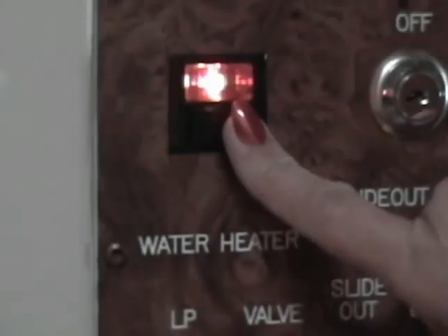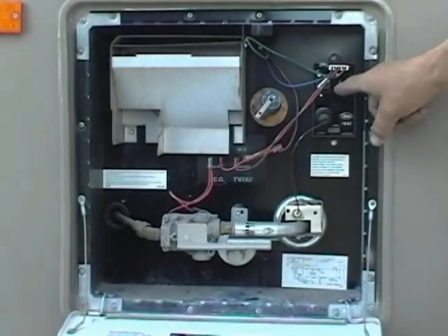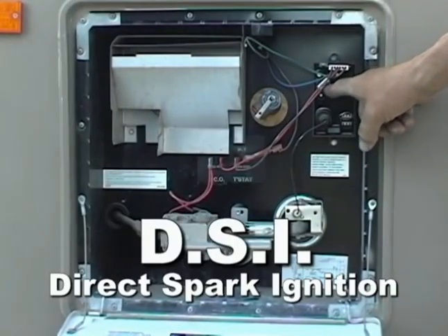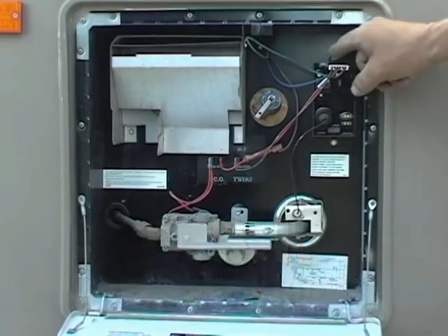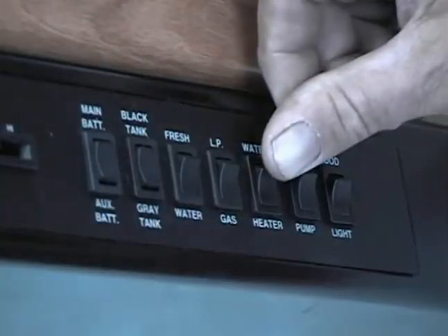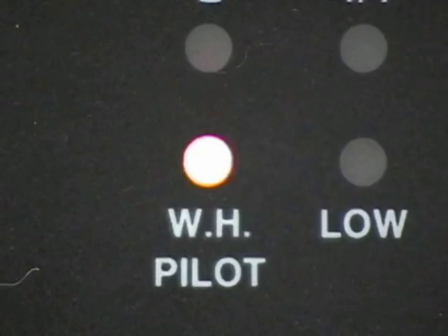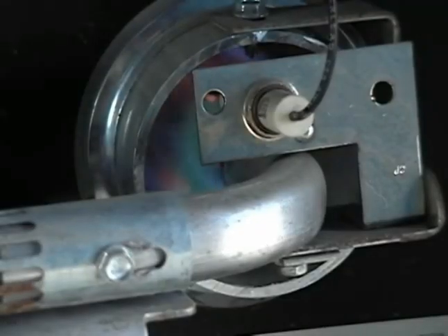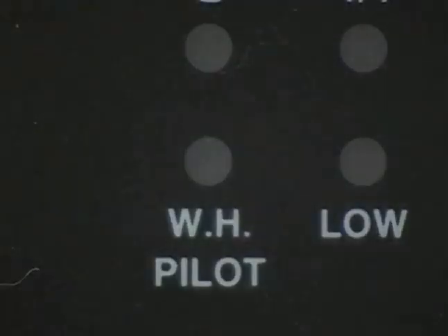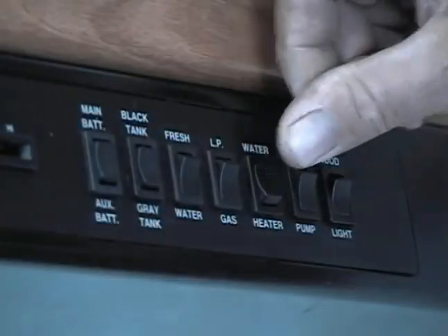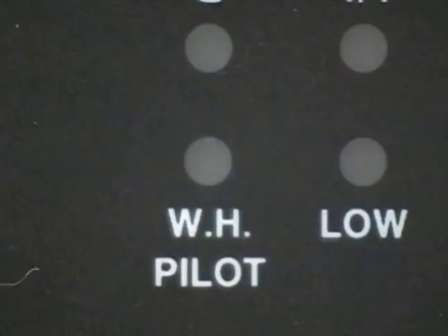Now let's move on to automatics, the DSI models, or direct spark ignition. These are very simple to operate. Make sure the propane is on and flip the switch. When you do, the light should come on. That's telling you that the process has begun. After a few seconds, the light will go out, and if the water heater fires and everything is okay, the light will stay off. When you flip the switch and the light doesn't come on, you may have a problem.